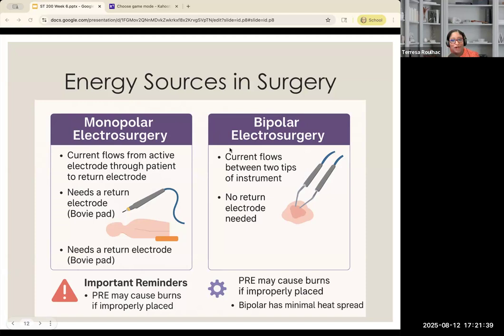For our bipolar, this one's a little bit different. Both active and return electrodes are on the same instrument. They're in between, so we do not use grounding pads for the bipolar. Why? Because the electricity isn't actually going through the patient. It's going through the instrument itself, and the current flows only between the two tips. There's no traveling through the body. So we don't tend to have a grounding pad.